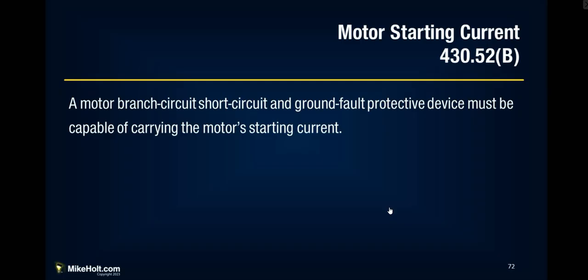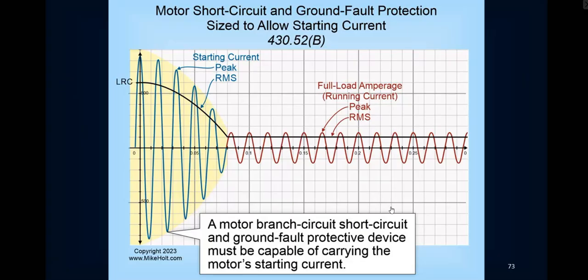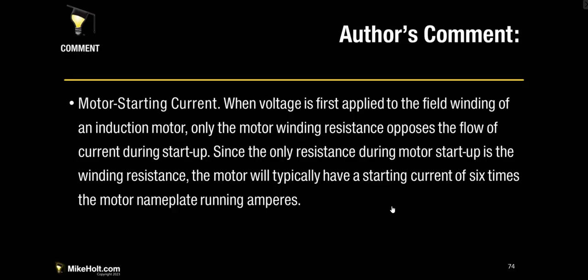You probably already know this, but when a motor starts, it's going to ramp up really high, and then it'll level off. But the overcurrent protection device has to be able to deal with that. And here's a little graphic showing that. Bang! It goes up really high, and I mean this is milliseconds, but once it takes off, then it's okay. But that overcurrent protection device has to be able to deal with that.